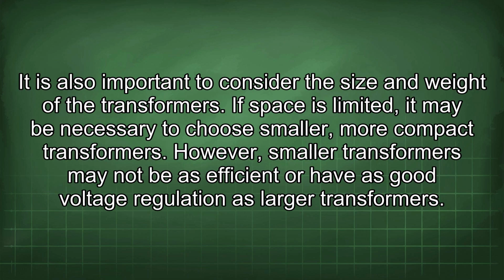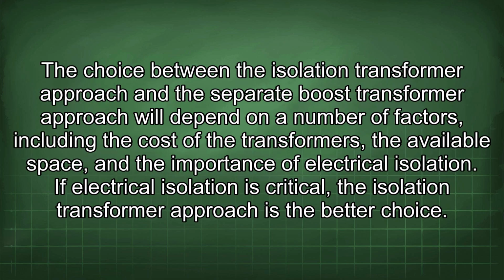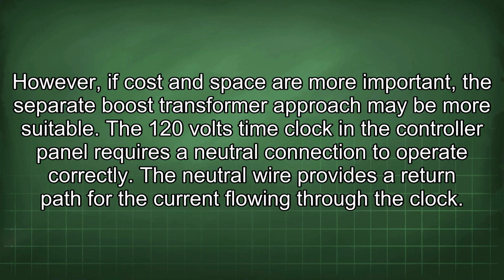It is also important to consider the size and weight of the transformers. If space is limited, it may be necessary to choose smaller, more compact transformers. However, smaller transformers may not be as efficient or have as good voltage regulation as larger transformers. The choice between the isolation transformer approach and the separate boost transformer approach will depend on a number of factors, including the cost of the transformers, the available space, and the importance of electrical isolation. If electrical isolation is critical, the isolation transformer approach is the better choice. However, if cost and space are more important, the separate boost transformer approach may be more suitable.